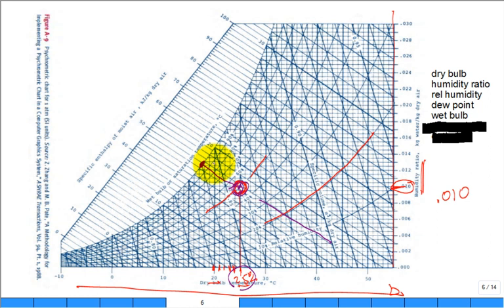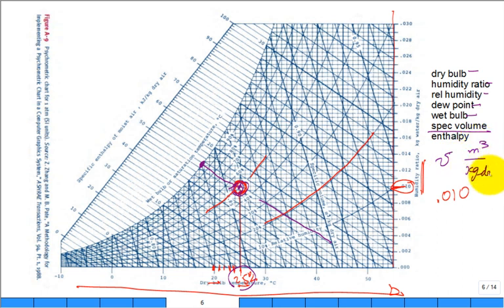So we've got the wet bulb and the dew point — those are three temperatures. We have two humidities. The other property is specific volume: how much volume per kilogram of dry air. Can you see a line of constant specific volume on the chart? It's sloped almost straight up and down but a little bit tilted. That constant value of specific volume reads as 0.90 — the units are cubic meters per kilogram of dry air.